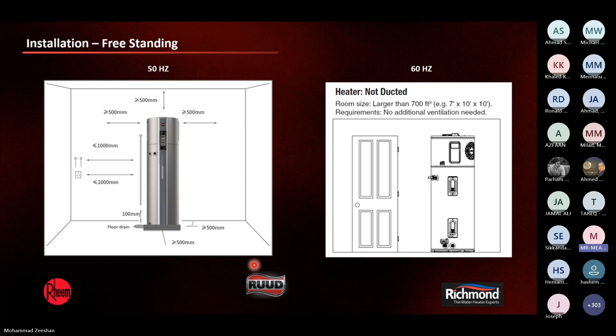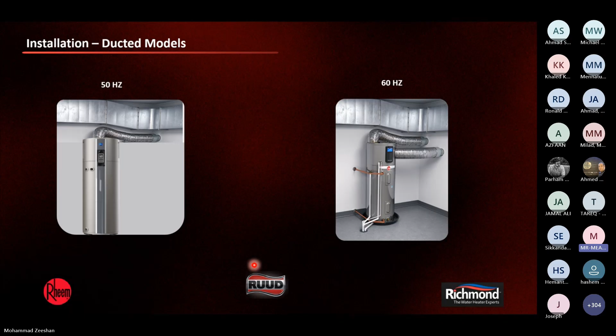When it comes to ducted models, you can also duct the units. In 50 hertz, you can duct the rejected air outside the room. So this gives you a bit of flexibility in reducing the room requirements and ensures that it can be installed in compact rooms. In 60 hertz models, you can duct both the inlet as well as the outlet, so the space constraints can be avoided easily. For the 50 hertz models, we have only the ducting at the discharge side. We have done several projects with this kind of design, and we've been very successful in such compact installations.